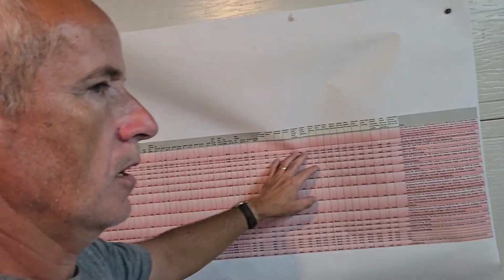So it progressively drops to get to the bottom of 1.64. So it's doing its job. It's slowly pulling all the moisture out of the air. So I'm kind of thinking that if we have 2 units, we can speed that up twice. I think maybe. I have gone over past statistics from other kiln runs when we just had the Nyle and it was working optimally.